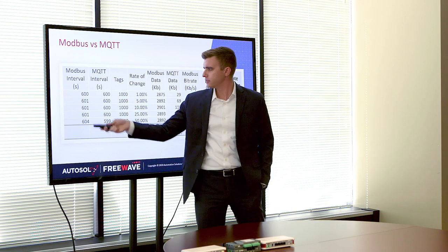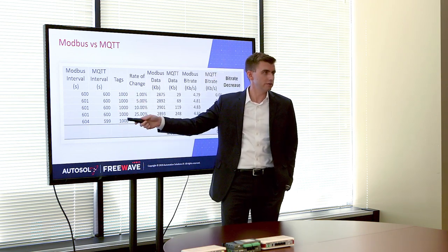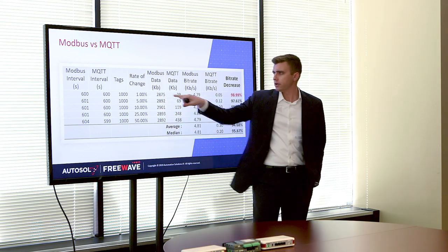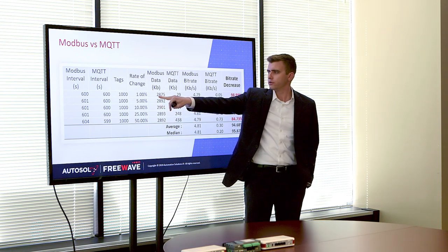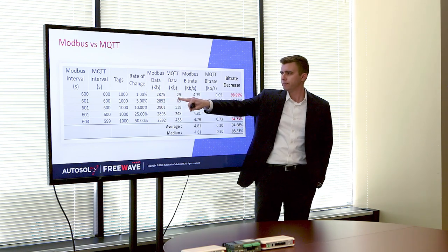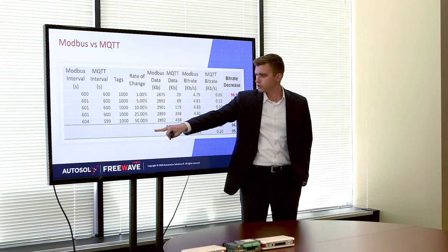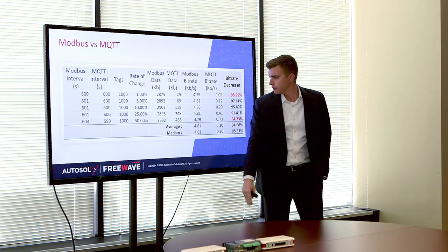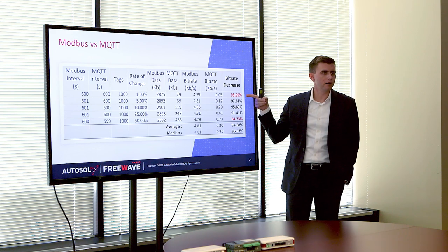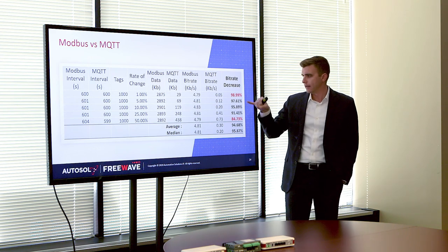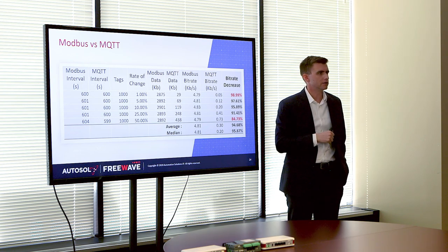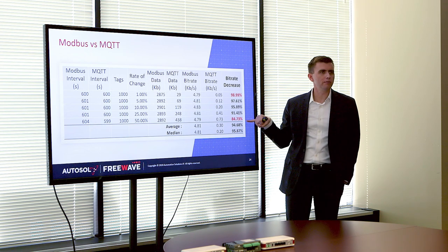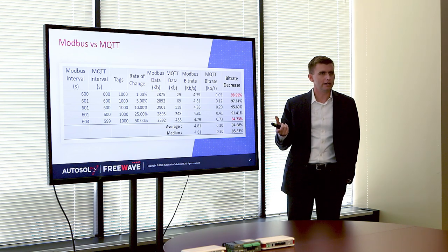Pulling Modbus and MQTT at the same time, these were the results. The same 10-minute time interval, 1,000 Modbus tags, rate of change 1%, 5%, 10%, 25%, and 50%. At a 1% rate of change, Modbus used 2,875 kilobytes — MQTT used 29. At 50% change of tags, Modbus used 2,892 — MQTT used 438. So basically, MQTT versus Modbus with a 1% rate of change is a 98.99% reduction of bandwidth consumption, and at 50% rate of change 84.73%. The relationship between bandwidth saved and rate of change is not linear — it's actually much more than one-for-one.